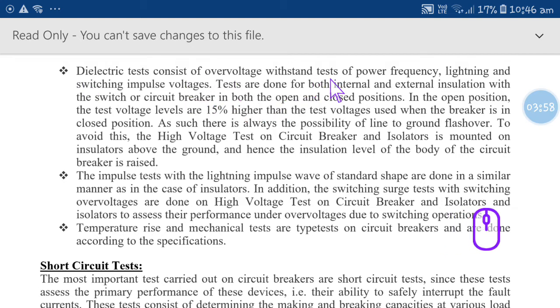These tests are done on both internal as well as external insulation of switches or circuit breakers, in both open and closed conditions. In the open position, the test voltage level will be 15% higher than the test voltage. An impulse voltage test is done with a lightning impulse voltage wave of standard shape, in a similar manner to how it is done on insulators.